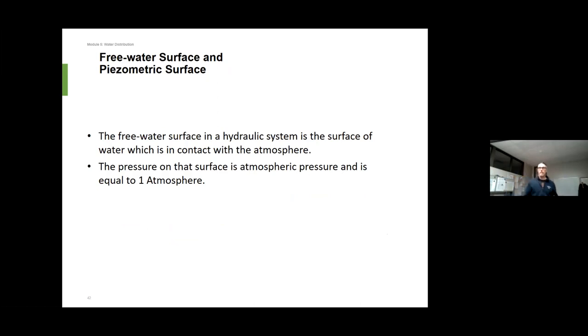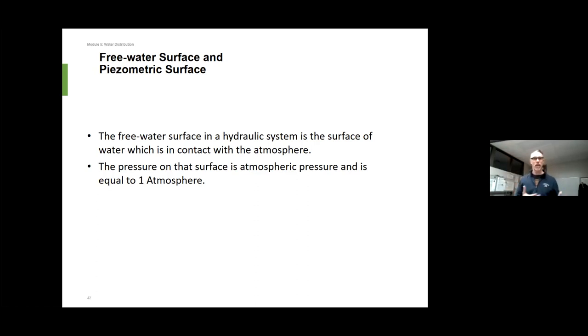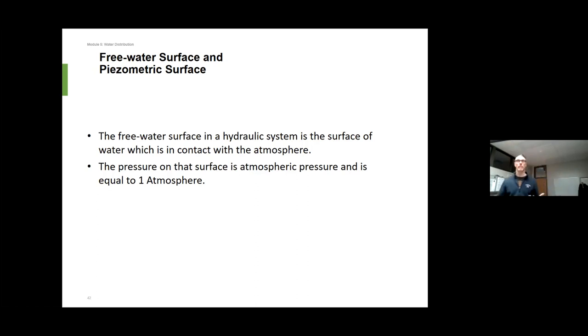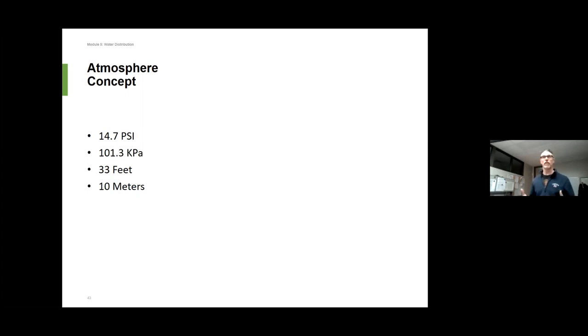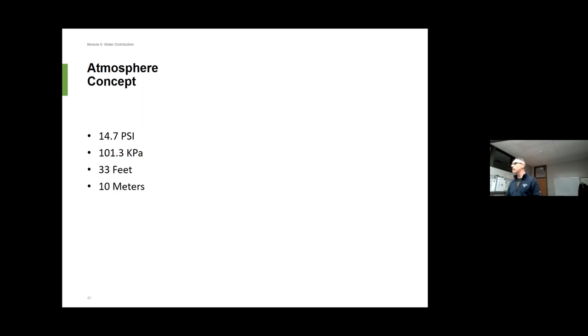Now let's talk about the piezometric surface, or free water surface in a hydraulic system. Basically it's the surface of the water which is in contact with the atmosphere. Whenever we pump water from one place to another, it starts open to atmosphere and ends open to atmosphere. The atmospheric pressure on the surface is equal to one atmosphere — 14.7 psi, 101.3 kPa, 33 feet, or 10 meters. If I have 10 meters of water in my reservoir, it's equal to 101.3 kPa. Level is equal to pressure — that's really important.